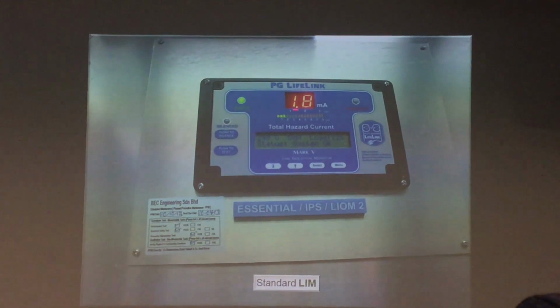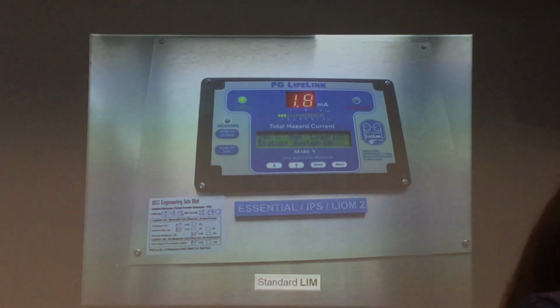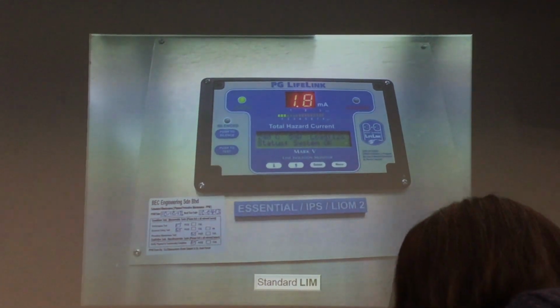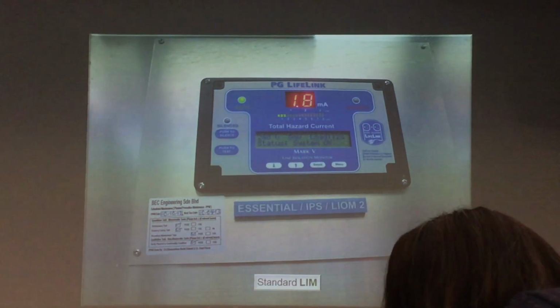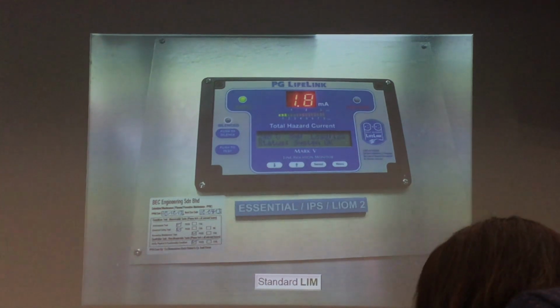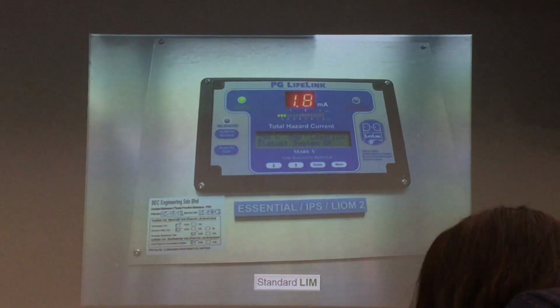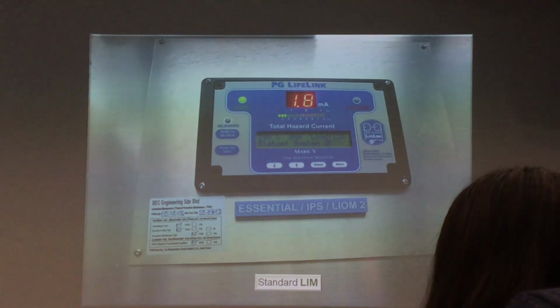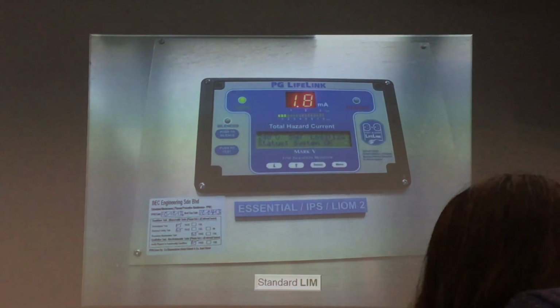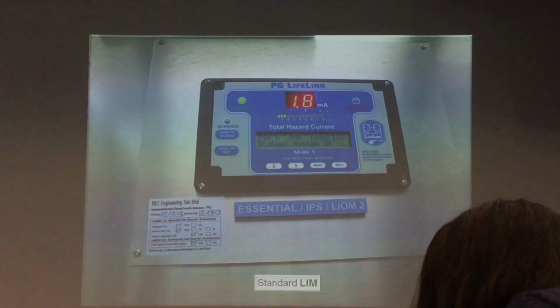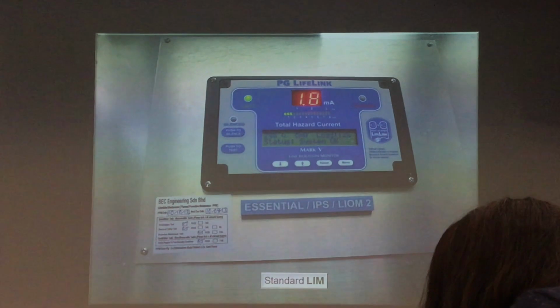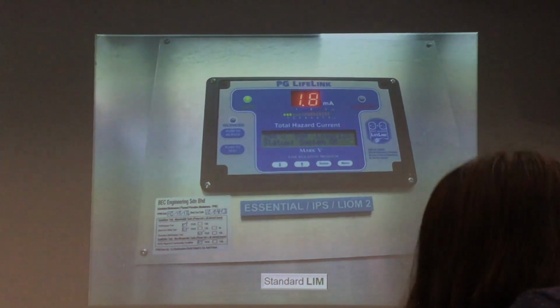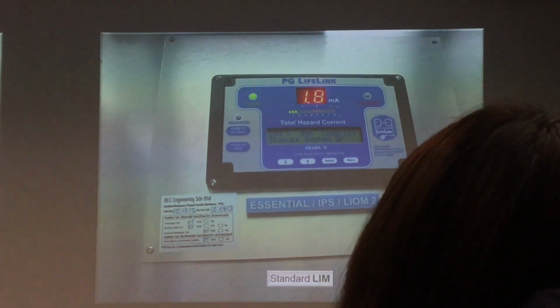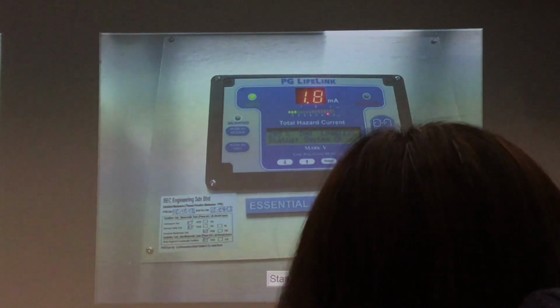So if the current is more than 3, it will give an alarm, indicating you are using more than you expected. You are using more than 3 mA, so be careful. Maybe you have to reduce, or stop, or use one by one. This is non-cardiac; cardiac is more. So this is just a warning. It doesn't prevent electrocution. They're using more than you're supposed to use. You are supposed to use, let's say, 2, not more than 3 at any time.